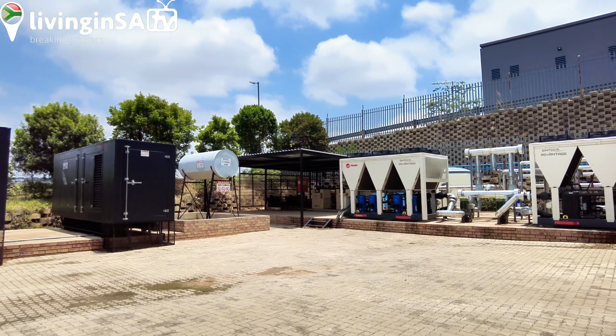Now let's go outside where we have the plant feeding whatever is happening inside. Outside the plant, we have our electricity supply, which gives us 2 MVA, and we have 2 generators, each giving us 1000 kVA. So when the electricity goes out, both generators come up, and then the system tells it that it only needs 1 generator, and switches off the other.